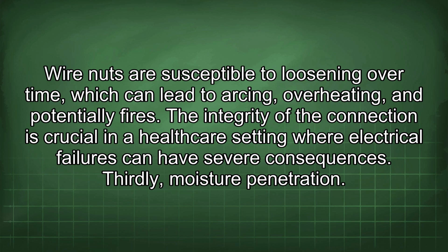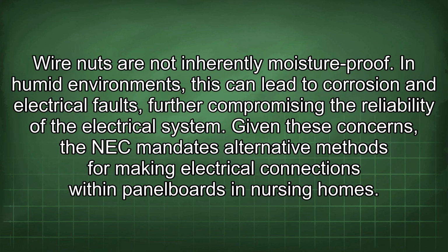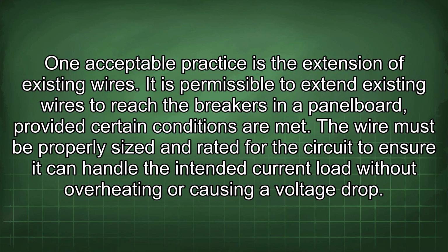Thirdly, moisture penetration. Wire nuts are not inherently moisture-proof. In humid environments, this can lead to corrosion and electrical faults, further compromising the reliability of the electrical system. Given these concerns, the NEC mandates alternative methods for making electrical connections within panel boards in nursing homes. One acceptable practice is the extension of existing wires. It is permissible to extend existing wires to reach the breakers in a panel board, provided certain conditions are met.